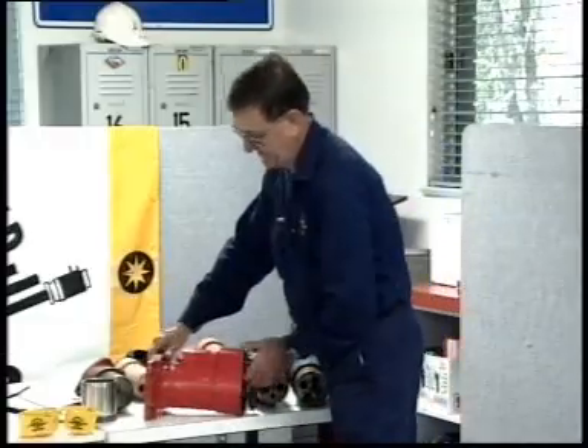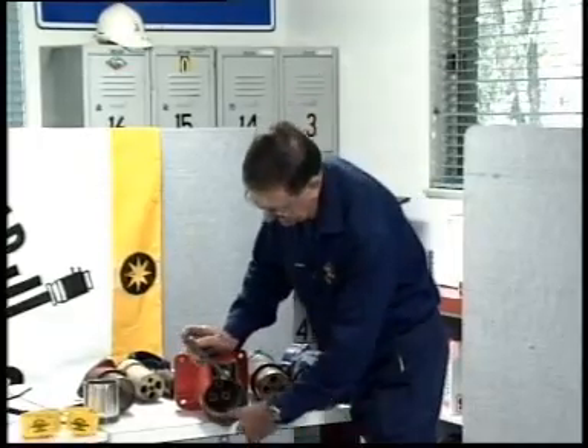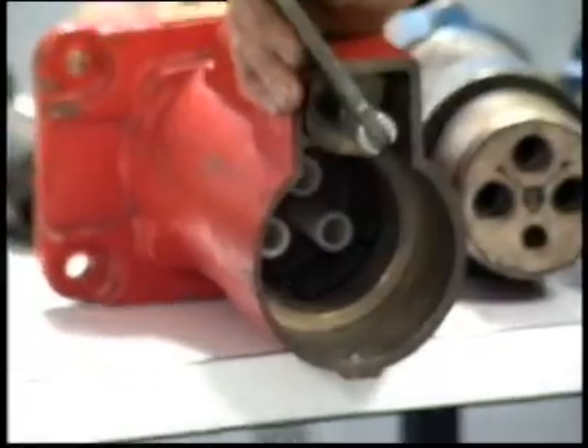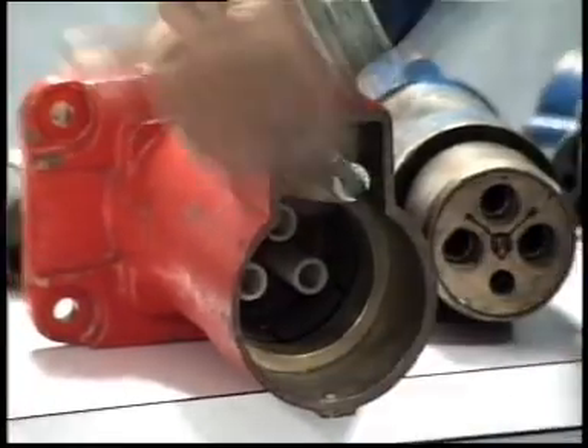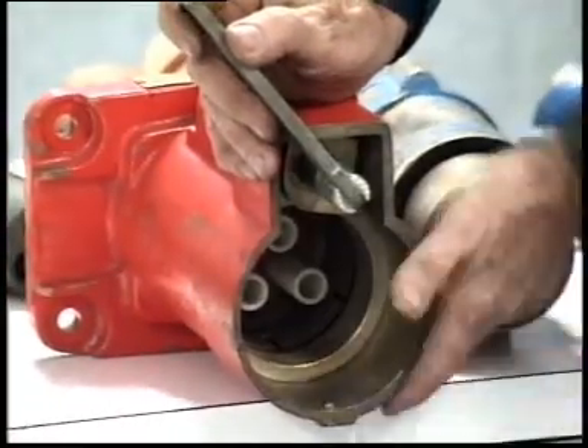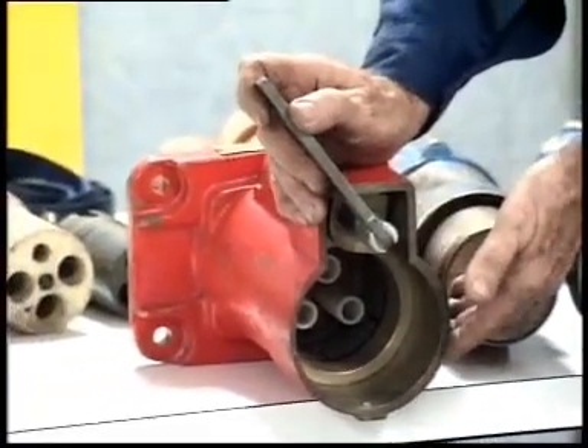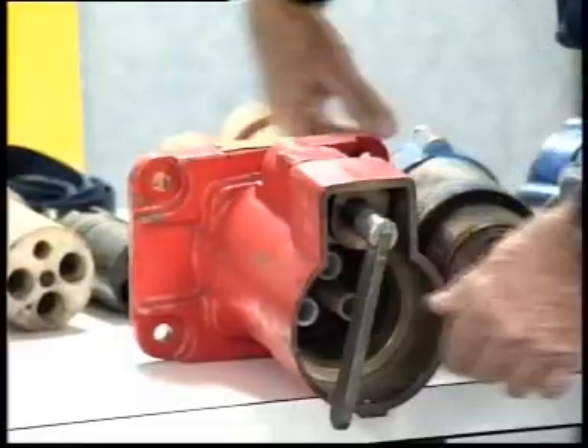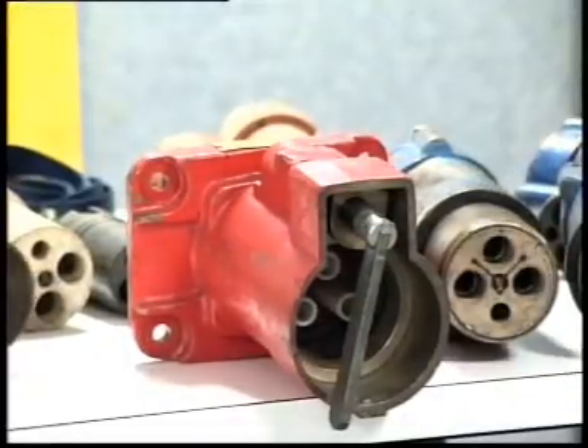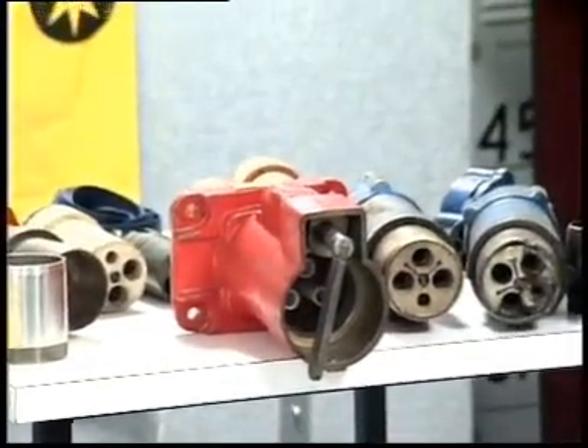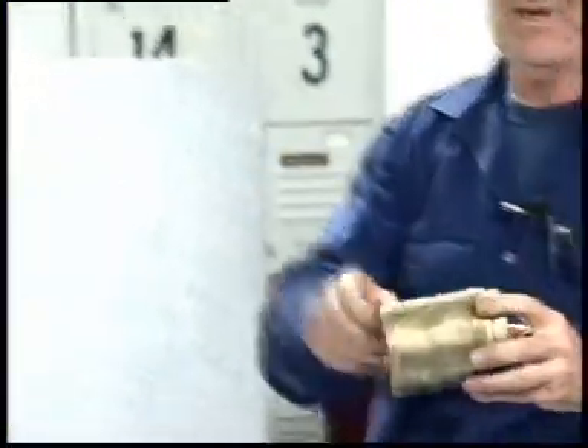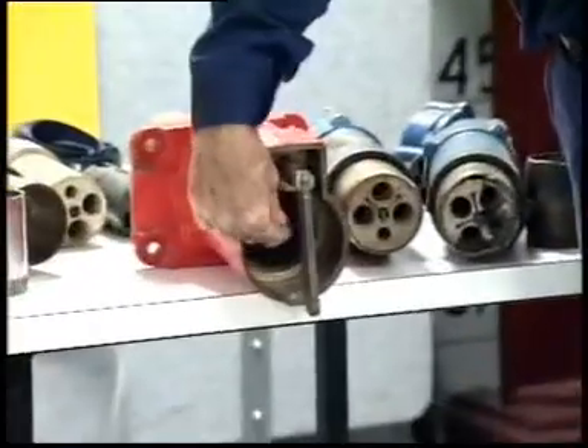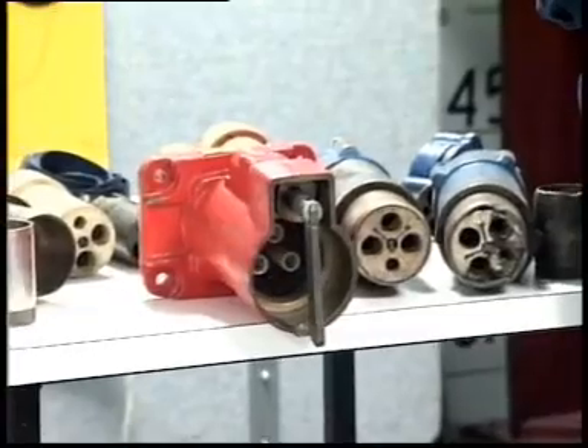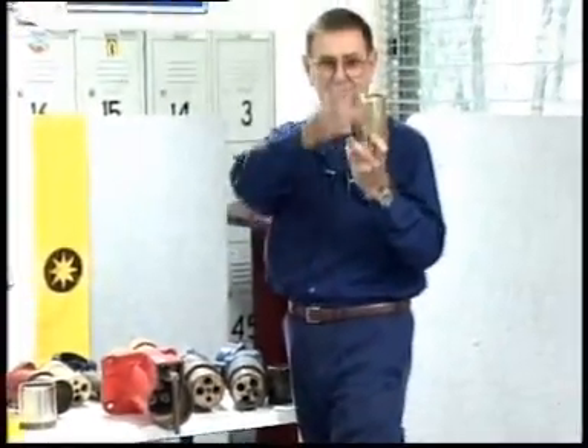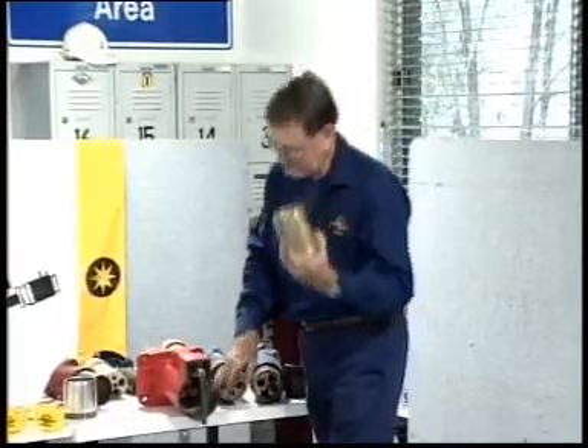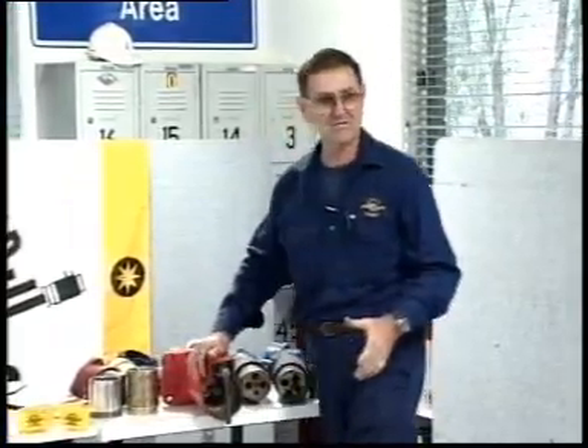So that's that one. We have a look at the front of it. There's also another flame path here. Where you see that brass collar, for a better word, inside there, if anybody wants to have a look at this after, come up and have a look. There's a brass collar sits inside there. It's part and parcel of this whole body. Where that's sitting is where the front end of the plug sits, which is one of these brass earth sleeves or earth skirts, we call them. So where that sits against that collar there, there's a flame path area. For today, we're going to treat the whole length of that as the flame path area on the plug, the whole length of it. Okay? That's also a flame path. Want to make sure it hasn't got any deep scratches or anything in it.